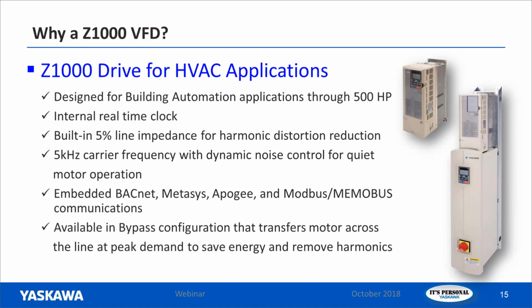All right, next we have several embedded communications: BACnet, Metasys, Apogee, and Modbus. And then also the Z1000 drive is available in bypass configurations, one that transfers the motor across the line at peak demand to save energy and remove harmonics. We call this an intelligent bypass. It's programmable. You don't have to use this feature, but it's a really good feature. You can set it up so that if it sees that it's running at peak demand for a certain amount of time, there's no real sense in having the drive in the circuit.